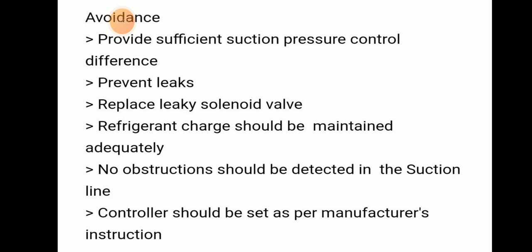To avoid short cycling: provide sufficient suction pressure control difference, prevent leaks, replace leaky solenoid valves, and maintain refrigerant charge adequately. No obstruction should be present in the suction line, and controls should be set as per the manufacturer's instructions.